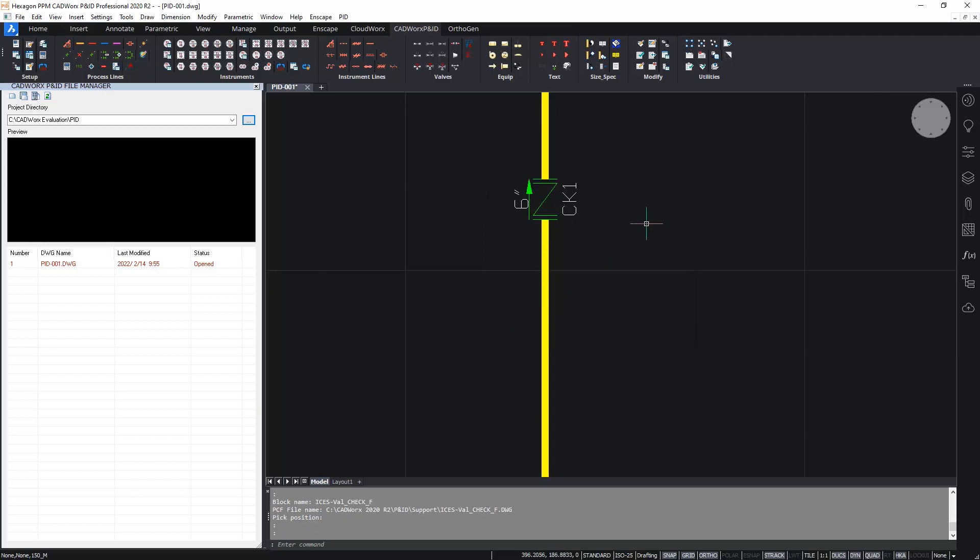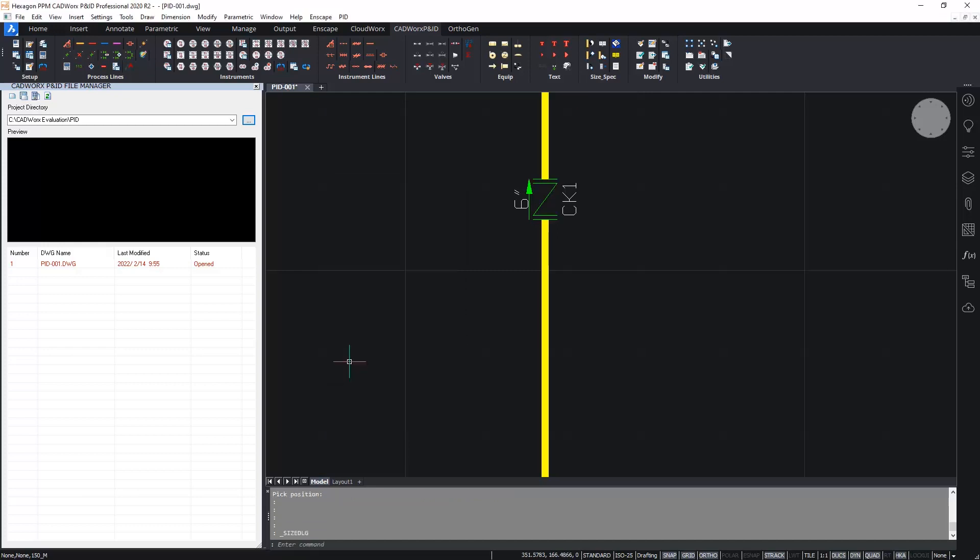Next, I'm going to place a reducer. Before I place the reducer, I'm going to set the main and reduction sizes. So I'll set, as we've already seen, a six inch main size and a four inch reduction size. And then on the reducers icon over here, I'm going to select the reducer, pick the concentric reducer symbol from the library.